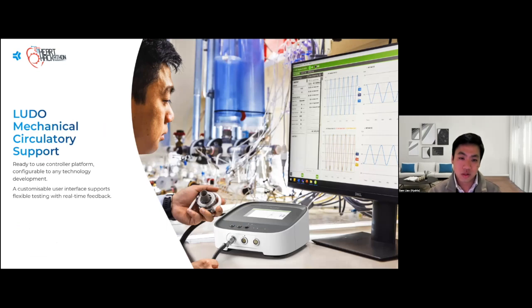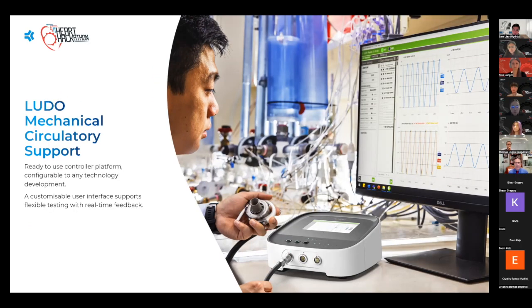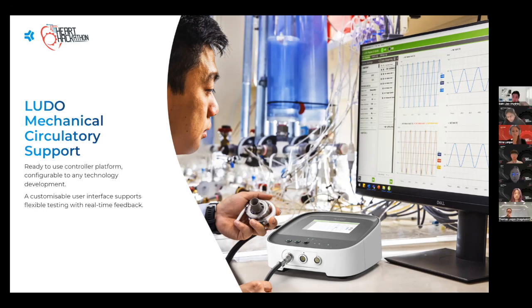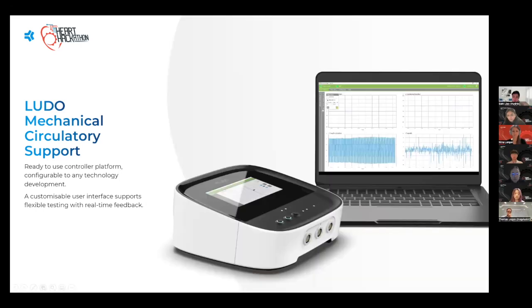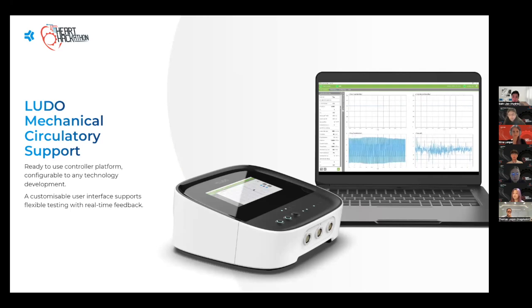So Ludo is a pump controller that is suitable for development from benchtop testing to first in human and beyond. The Ludo platform greatly reduces the development time of controllers, as Ludo has been designed with a safety critical architecture from the ground up and is suitable for Class 3 medical devices. So essentially, the platform allows the pump development to be more streamlined.